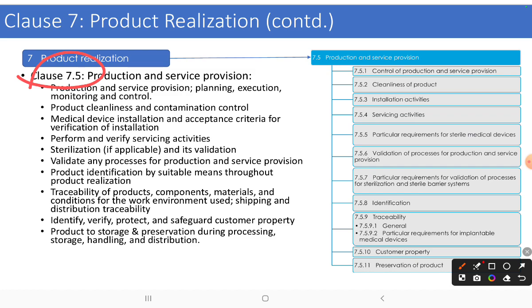Planning, execution, monitoring and control. We should have a documented process for planning, execution and monitoring its control, and for product cleanliness and contamination control. So the day-to-day hygiene of the manufacturing operations, how that will be maintained. Once the product is ready, then for medical device installation, acceptance criteria for verification of the installation. So when we are selling any medical device to the customer, how it will be installed, what will be the acceptance criteria for verification of installation. The installation activity should be documented, verified, approved.